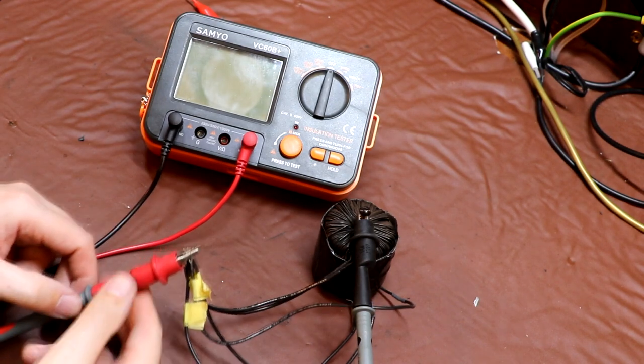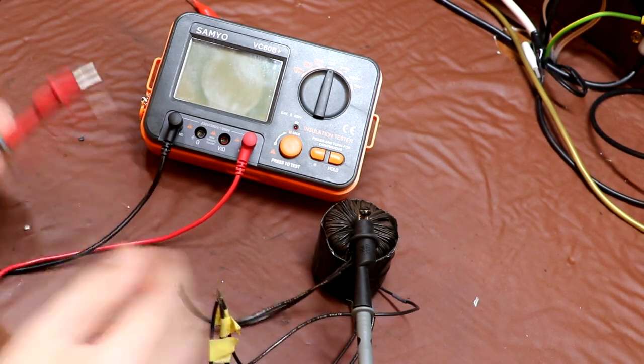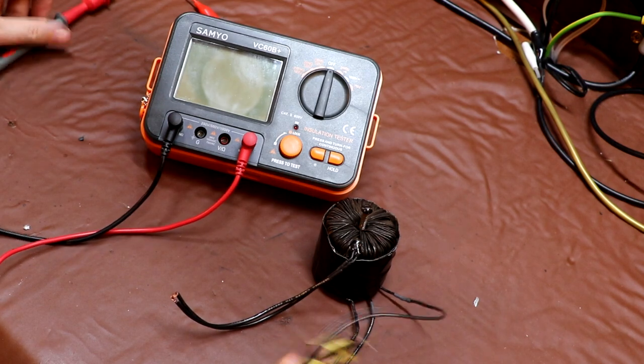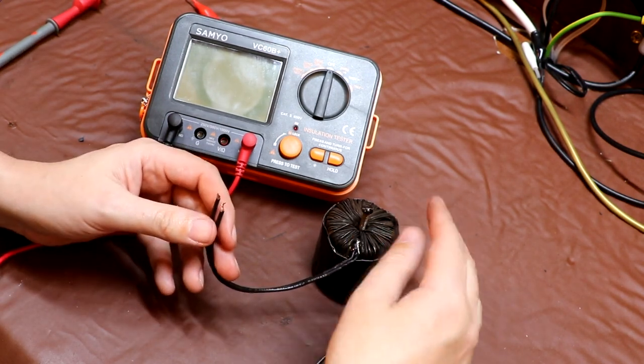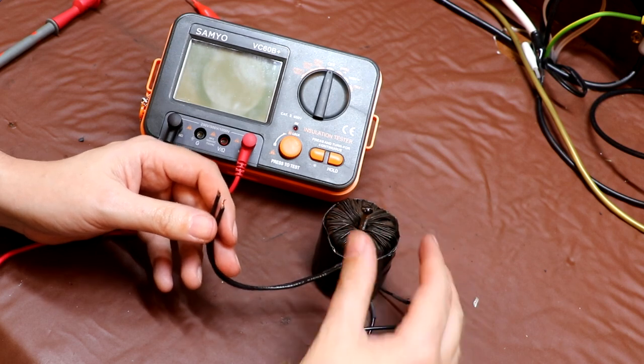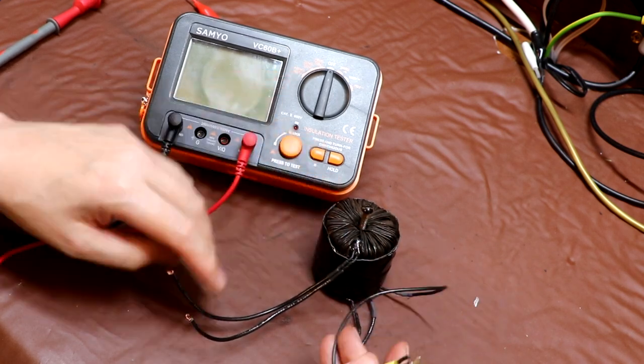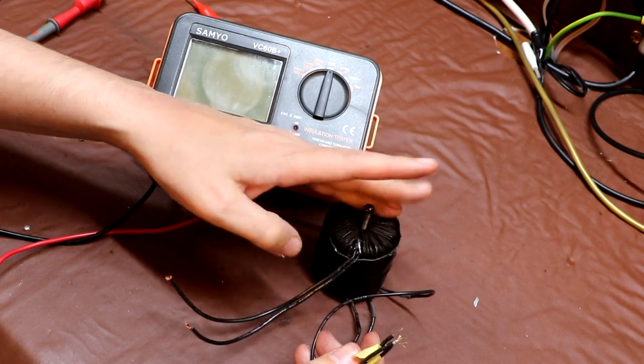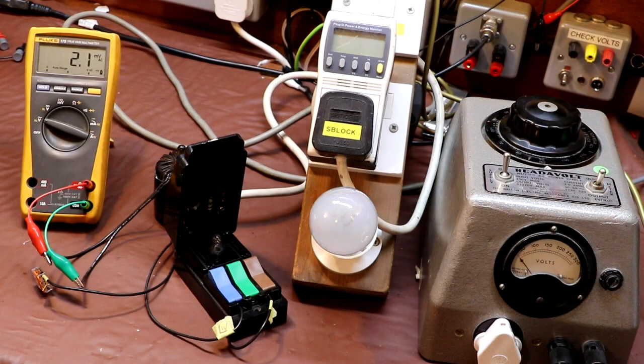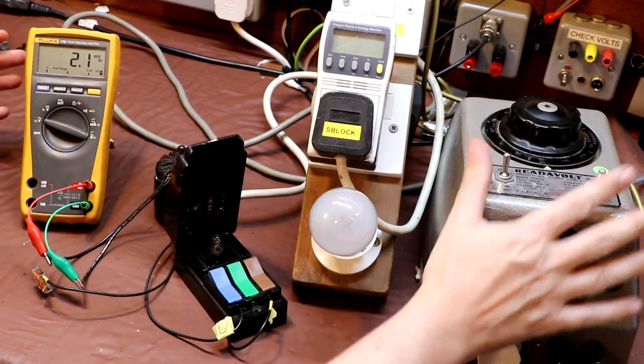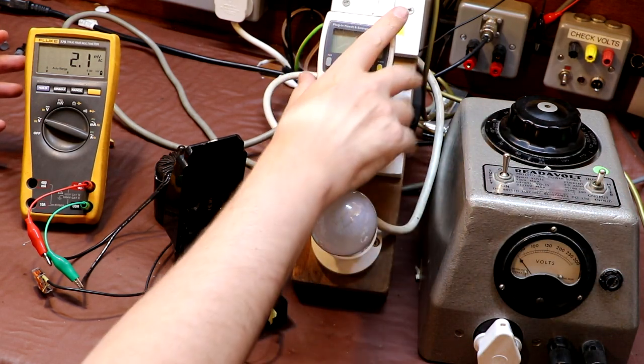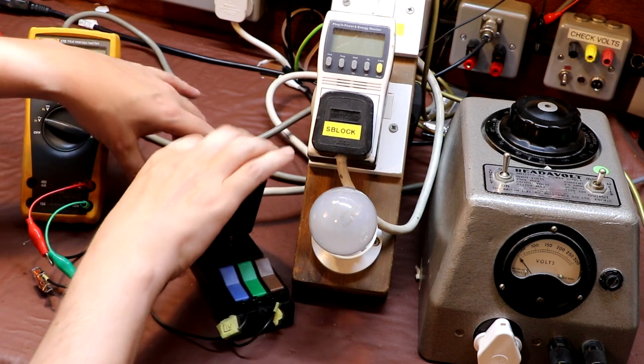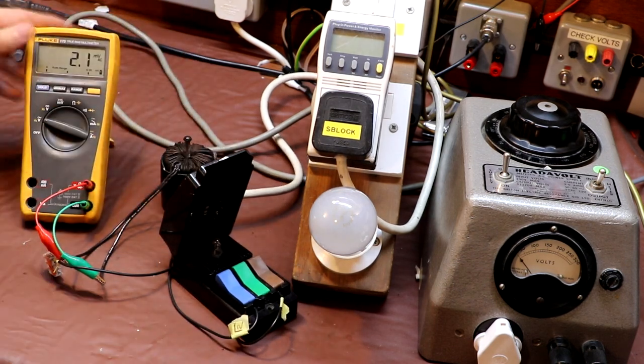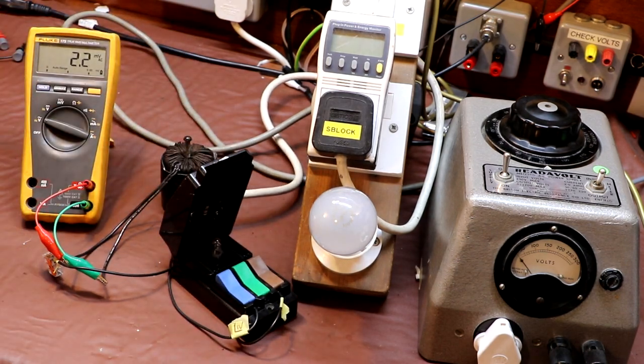Okay, so from an electrical safety point of view, certainly there aren't any short circuits between the primary and the secondary, or any of the windings to the core. So in theory, we could apply power to this and then touch the transformer and we shouldn't get an electric shock off it. Well, as you can see, I've gone ahead and got out the variac and the lamp limiter, and I've got a watt meter here which is also going to read off our voltage. Got our transformer tucked away in the background, and we've got a voltmeter which is connected to our secondary.